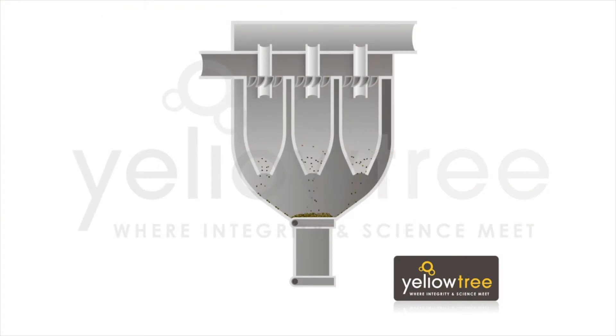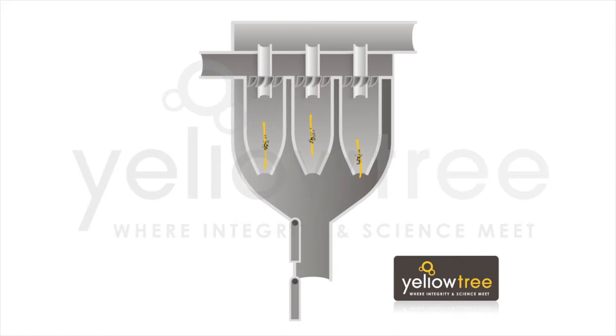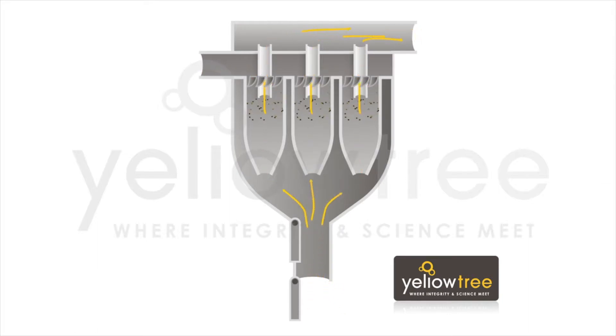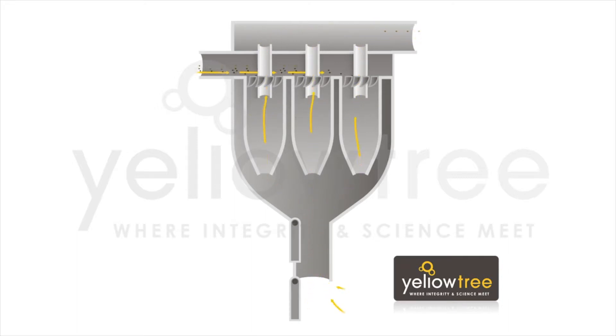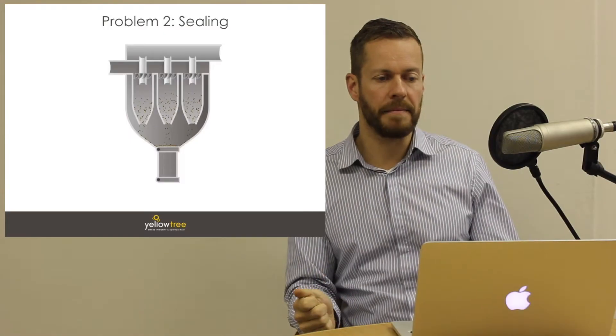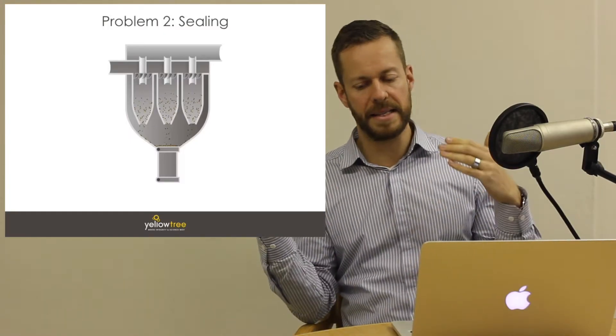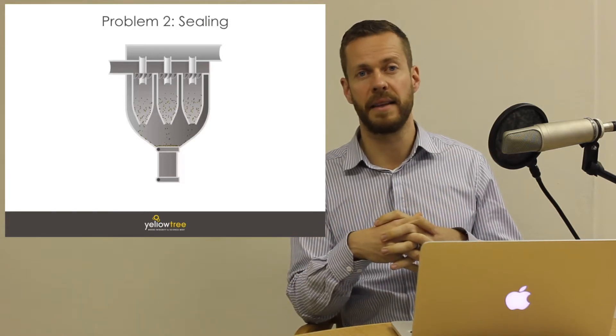The video shows that when the particulate matter is correctly arrested — sitting on the first flap, then the second flap — but then both flaps remain stuck open because they're broken or jammed, air gets drawn in. That air captures all of the particulate matter and takes it out the chimney stack, which we don't want. In addition, air flowing up through the sealing flaps disrupts the vortexes in each cyclone, so we no longer have the centrifugal force needed for separation, and all the particulate matter simply exits in the clean gas stream.